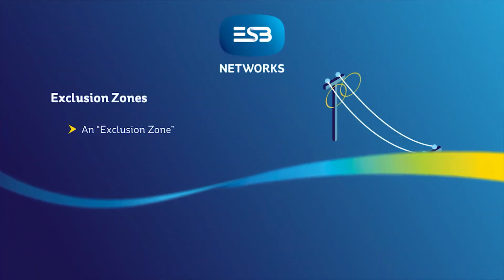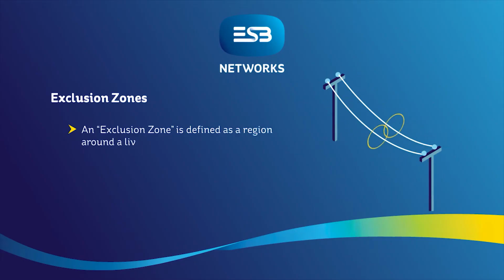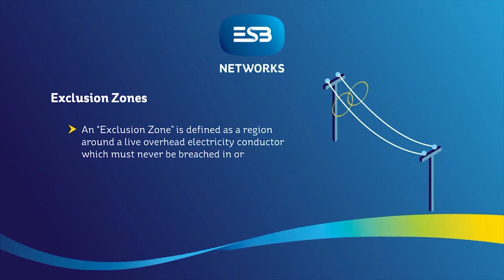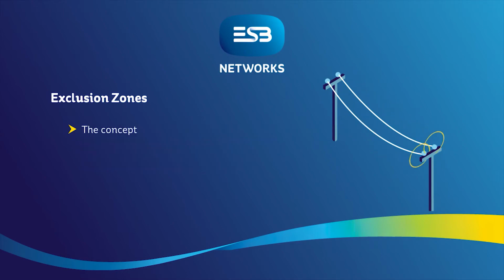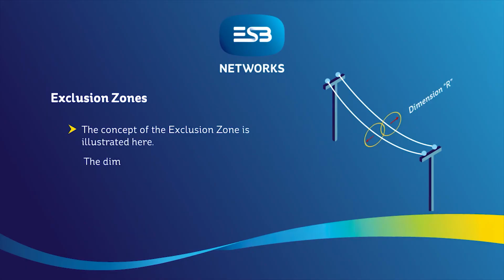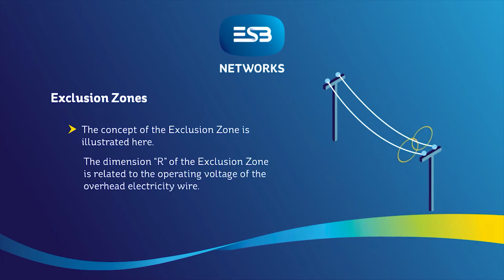An exclusion zone is defined as a region around a live overhead electricity conductor which must never be breached in order to avoid electrical arcing or flashover. The concept of the exclusion zone is illustrated here. The dimension R of the exclusion zone is related to the operating voltage of the overhead electricity wire.